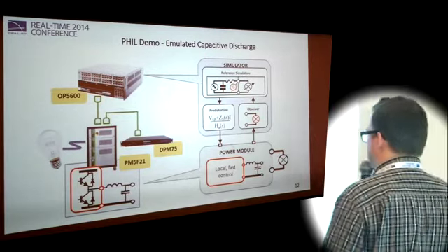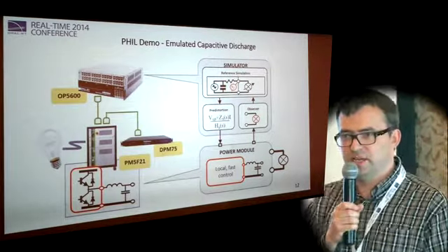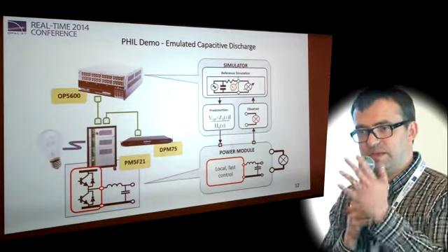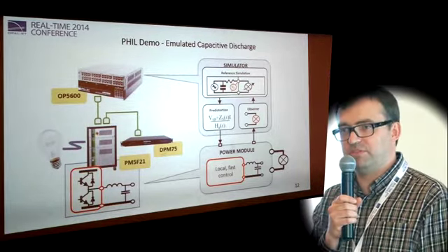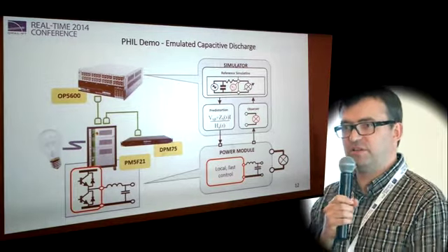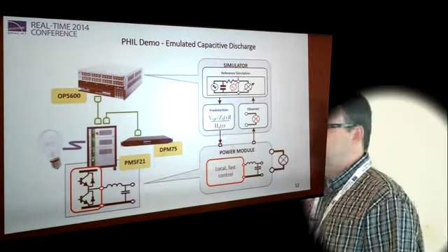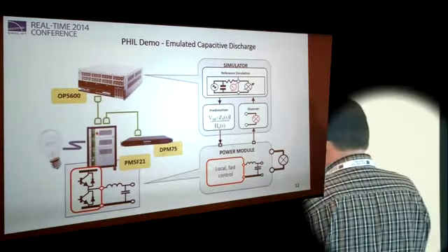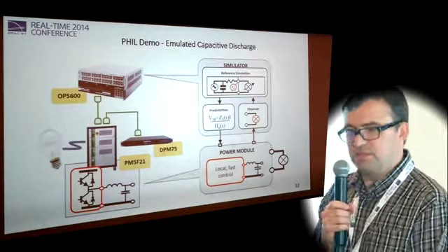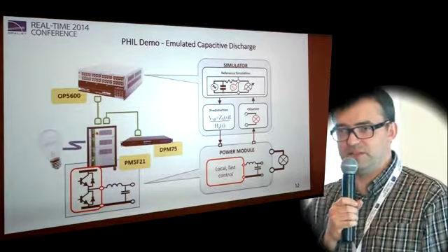When I gave figures about the dynamics, that is full range dynamics. When I talked about 250 to 400 microseconds, that's full range dynamics, from minimum negative current to maximum positive current. Anything faster than that, okay, we can have a discussion. It's possible in theory to account for it, but then you're again in the real-time simulation model.